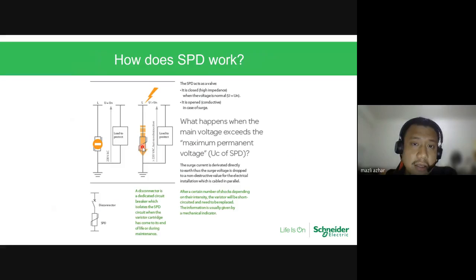Okay. So how does an SPD work? If you take an MCB and RCCB now, you turn it on, you can see there is a continuity. You take a multimeter, there is continuity on the top and the bottom. But SPD, there is no lever. Okay, on and off lever, there's nothing. It's a plain thing. But without operating at the common condition, it is an open circuit. Okay, it's not a closed circuit. So at the normal condition, you can see here is an open circuit.